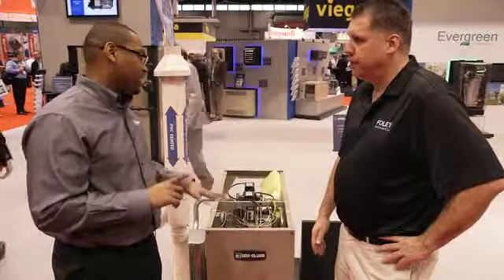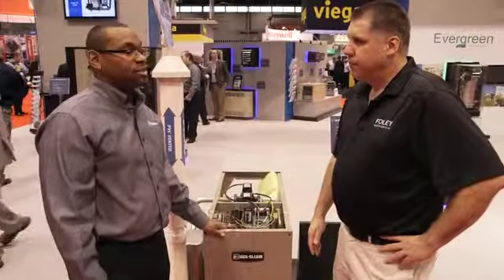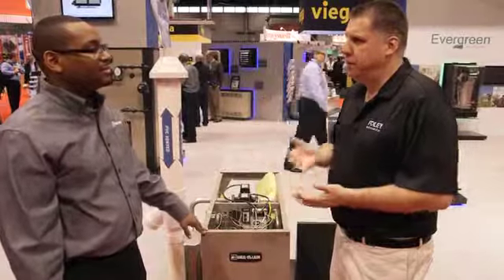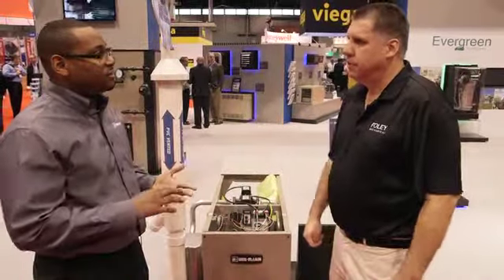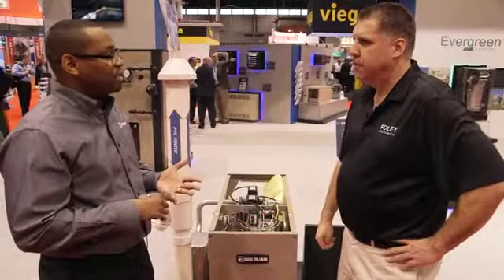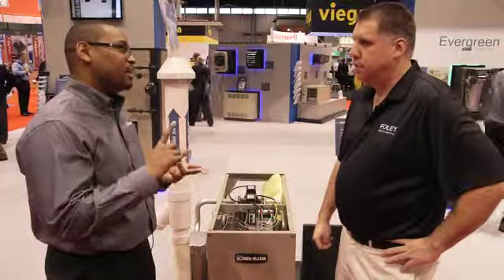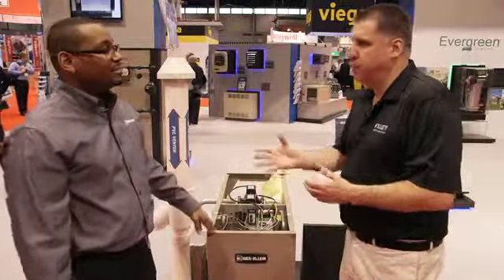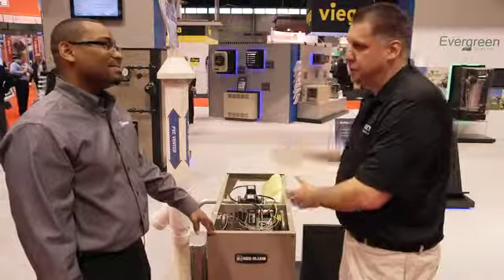And what we use is each high efficiency boiler is shipped with Sentinel X100. So you just dose that right into the system, and then you're good to go. And what is that? That's an oxygen inhibitor or a corrosion inhibitor? It's a corrosion inhibitor. It has seven different types of inhibitors inside of it, so it can deal with a variety of materials like copper, black iron pipe, stainless steel, you name it. So you're really looking out for the contractor when they put your product in. You're going to protect the boiler, the piping, and the radiation with the system.